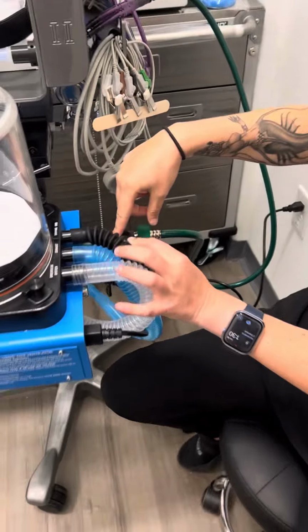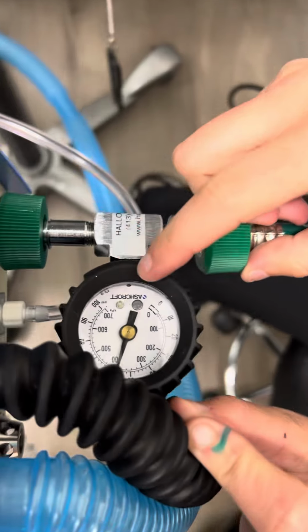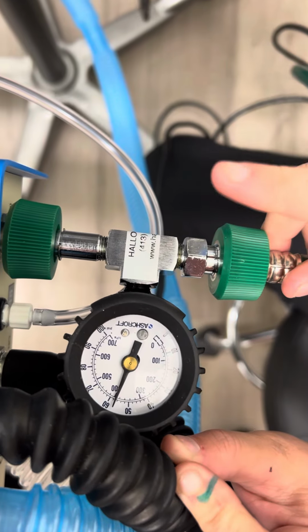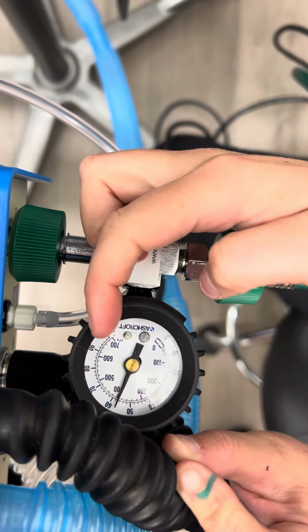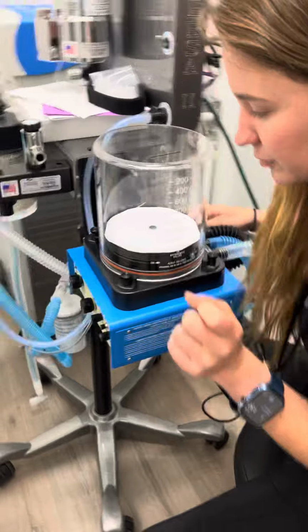And then here, I'll have you look at this manometer. Whenever the oxygen is hooked up to the drop down, if it's not at 50 psi, that's not enough oxygen being supplied to the ventilator, so it's going to sound the low pressure alarm.